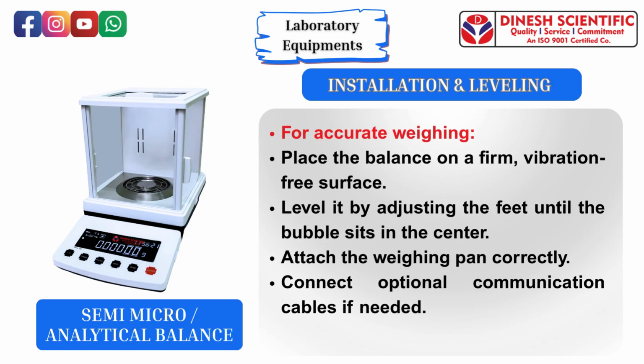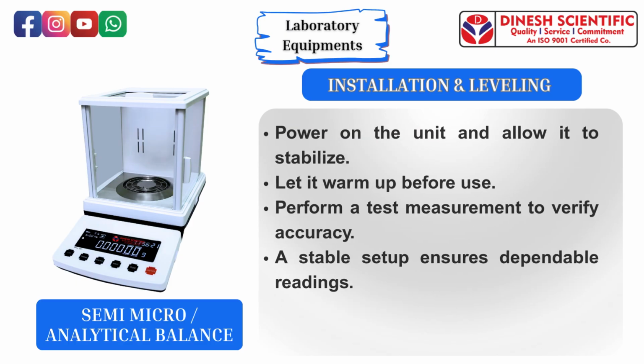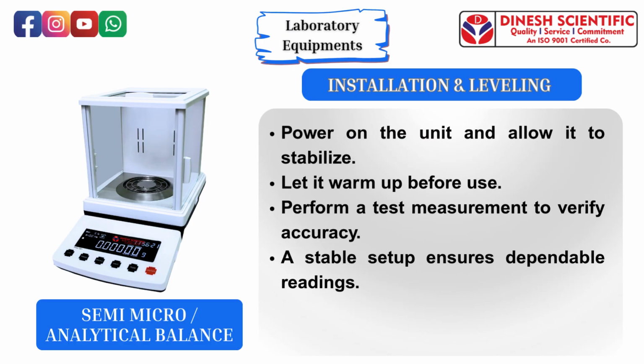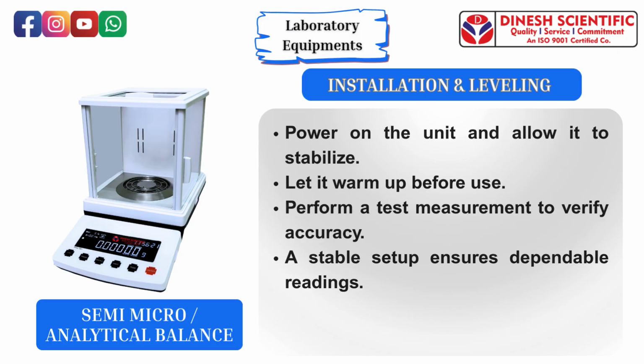Installation and leveling. For accurate weighing, place the balance on a firm, vibration-free surface. Level it by adjusting the feet until the bubble sits in the center. Attach the weighing pan correctly. Connect optional communication cables if needed. Power on the unit and allow it to stabilize. Let it warm up before use. Perform a test measurement to verify accuracy. A stable setup ensures dependable readings.